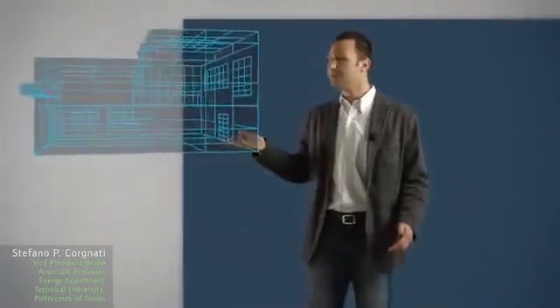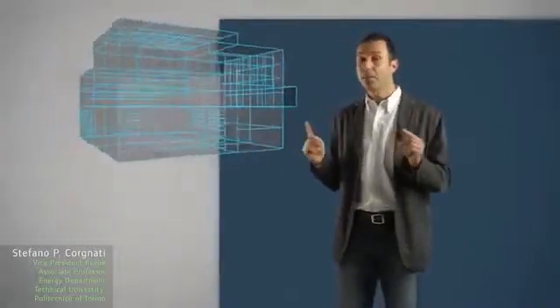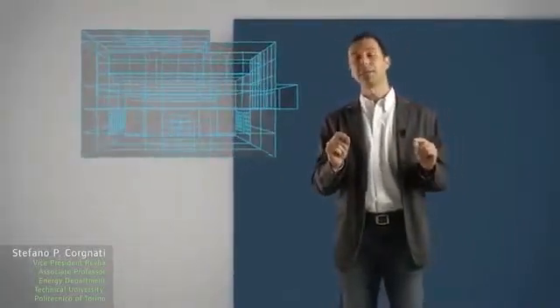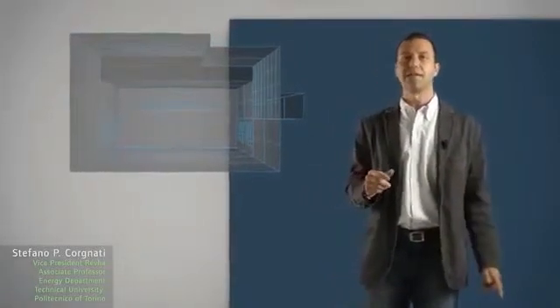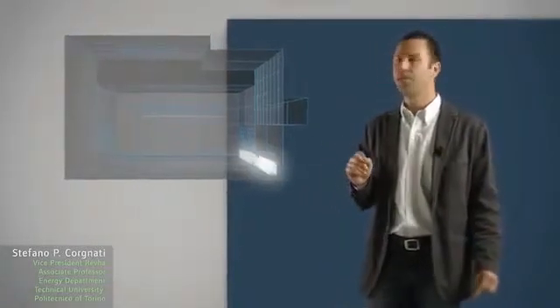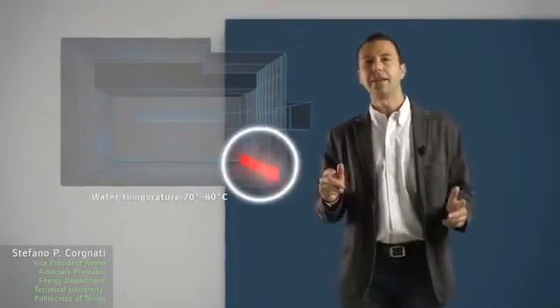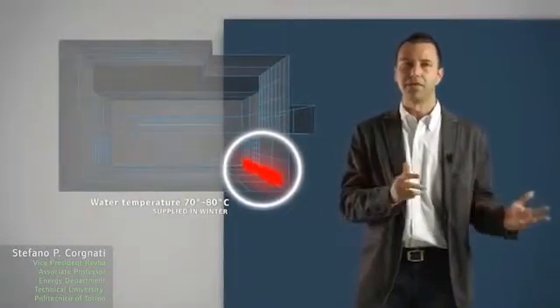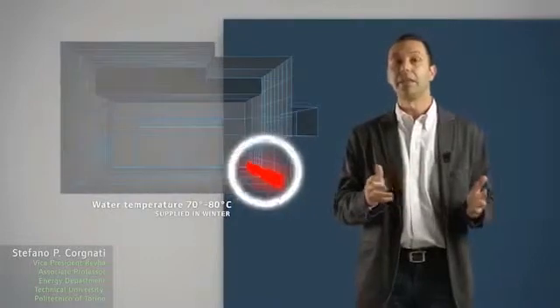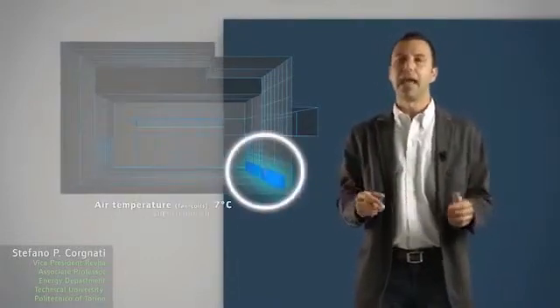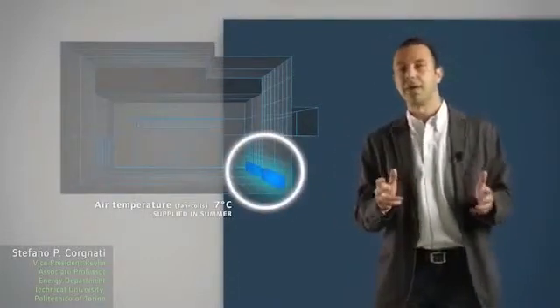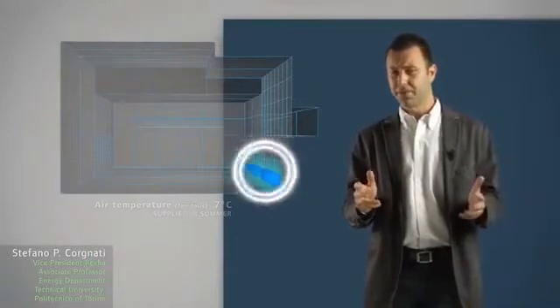In fact, traditional HVAC systems are characterized by an opposite functioning principle with respect to radiant systems. HVAC terminal devices are located in a specific point of a room, and high temperature water is supplied in winter, around 70-80 degrees for radiators, and low temperature in summer, around 7 degrees for fan coils.